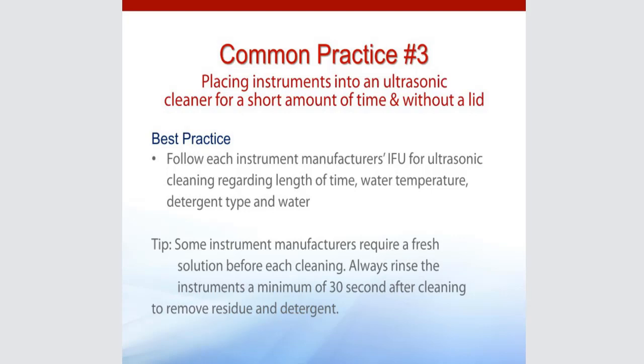Last but not least, we want to take the time to rinse our instruments after they come out of the ultrasonic. Sometimes we turn on the faucet and we do the quick one-two swish swish and we dump them out, and then we wonder why our instruments are getting the brown little pits on them, and it's because the enzymatic detergent was not adequately rinsed and you've essentially baked it on your instrument. So a minimum of 30 seconds before you're good to go.